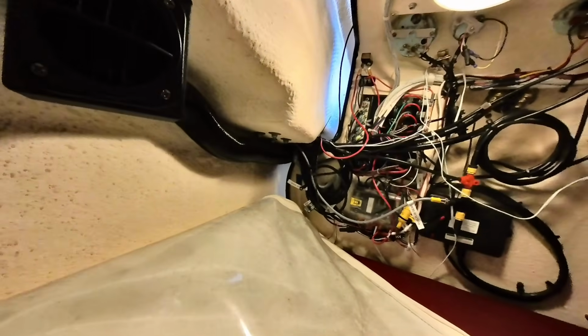I wanted to upsize that. It's clear that we get a big voltage sag when we fire up the diesel heater. I can see the lights dim. When the diesel fuel pump is running, I can see the lights flicker a little bit. And of course I can see the voltage drop on the Garmin display, so I know we're losing voltage. That simply means we don't have enough wire capacity to transfer that much current from the batteries to this distribution panel where it goes out to things like the heater. So we're going to upsize the wire.